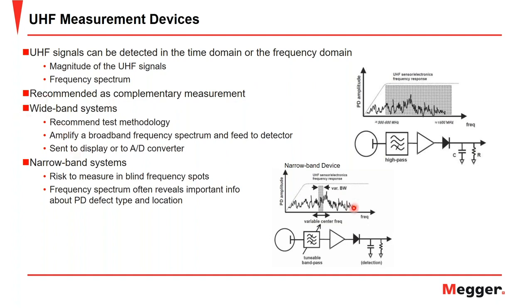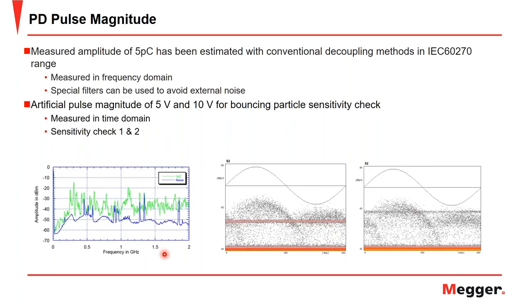Here we have a narrowband system, and you can see the difference where instead of looking at the entire PD signal, you're just looking at this small window. And on narrowband systems, you run the risk of measuring in blind frequency spots. And the frequency spectrum often reveals important info about PD defect types, as well as their location. So running the risk of measuring in a blind frequency spot can really be detrimental to the overall measurement. And here we have the PD pulse magnitude. So this is where we go into the sensitivity check.